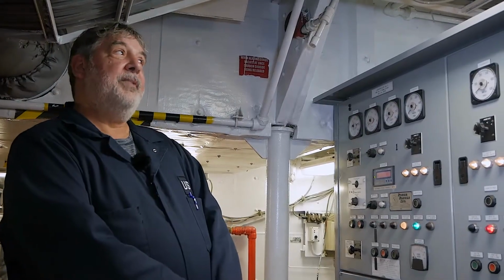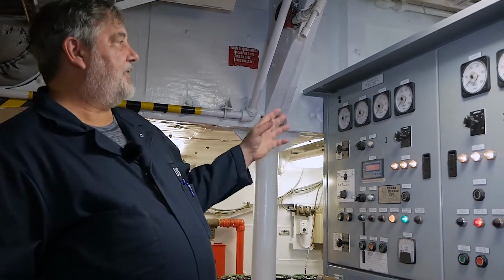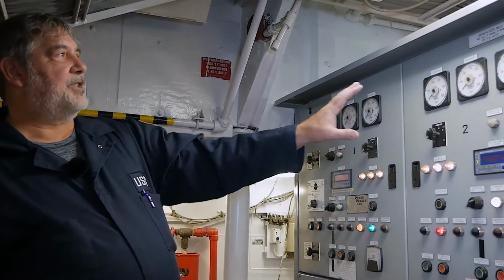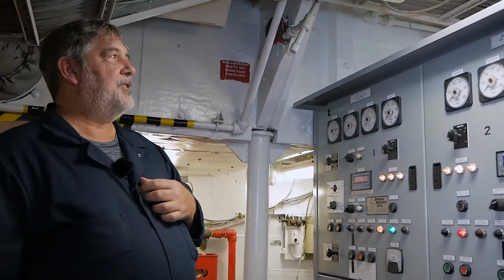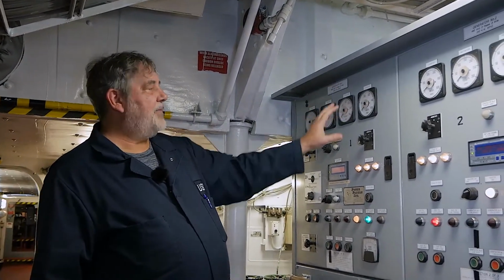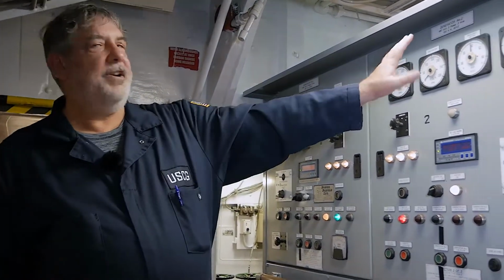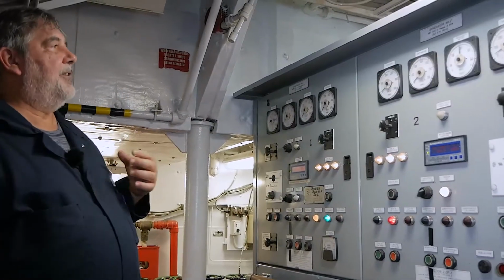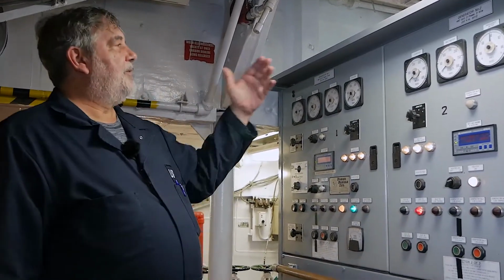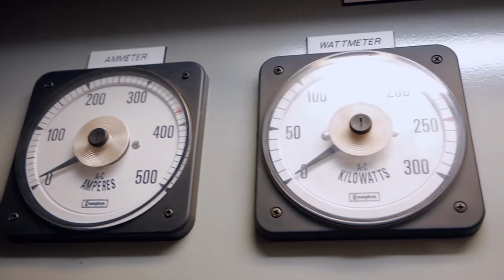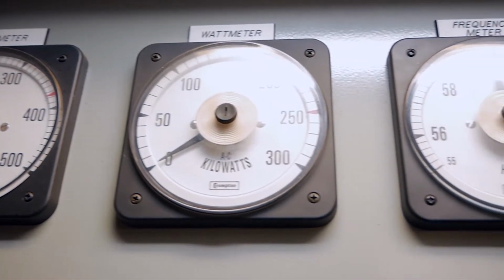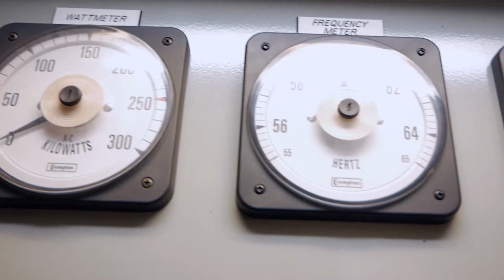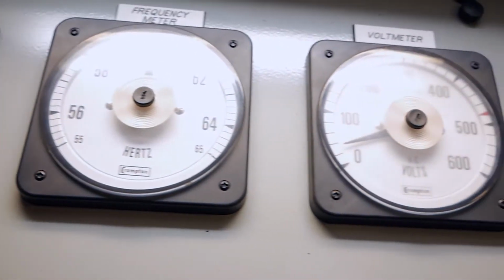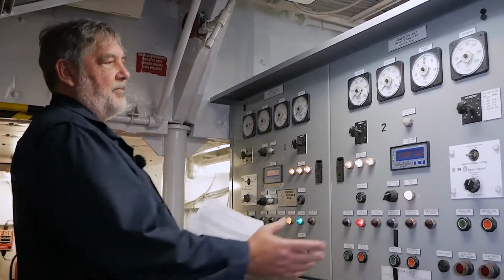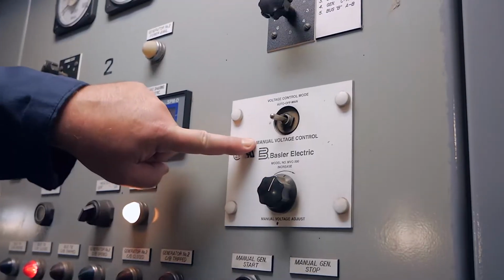Okay, let's talk about the meters and the controls that you'll find on a switchboard. As you can see, we have a switchboard that has number 1 and number 2 generators feeding into it. We'll have all of the meters and controls for number 1 generator and the meters and controls for number 2 generator. The standard meters are an amp meter, a watt meter or a power meter, the frequency meter, and the voltage meter.